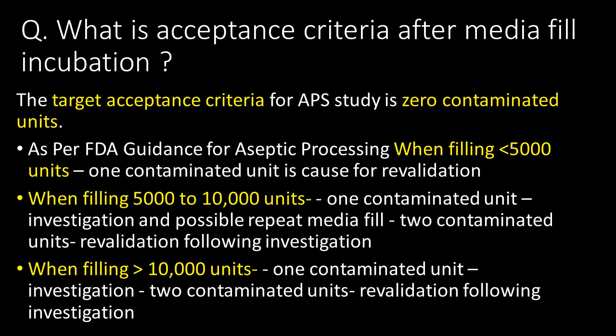What is the acceptance criteria after media fill incubation? The target acceptance criteria after aseptic process simulation study is zero contaminated units. As per FDA guidance for aseptic processing: when filling batch size is less than 5,000 units, one contaminated unit is cause for revalidation; when batch size is between 5,000 to 10,000 units, one contaminated unit will cause investigation and possibly repeat media fill.